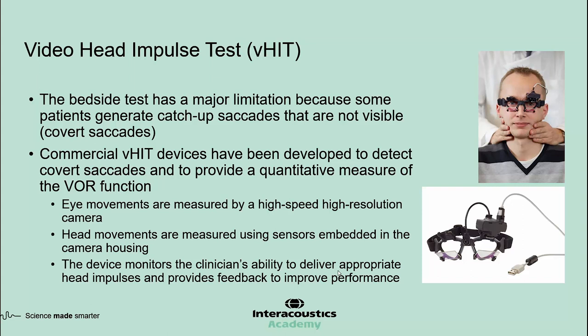In the 1990s, scleral search coils were used for identifying covert saccades and quantifying the head impulse test, but that method is not practical for routine clinical testing. Around the year 2010, the video version of the head impulse test became available commercially. In VHIT, eye movements are recorded and analyzed by high-speed cameras, and head movements are measured by motion sensors embedded in the goggles. The device can monitor the clinician's ability to deliver appropriate head impulses and provide feedback to improve performance.